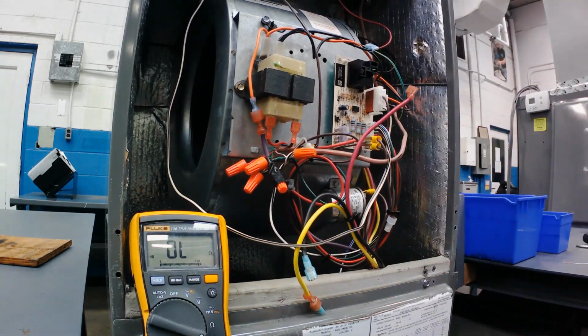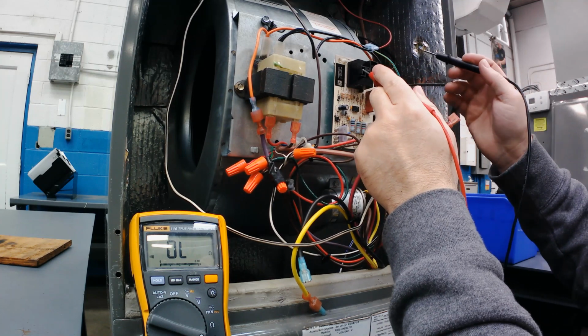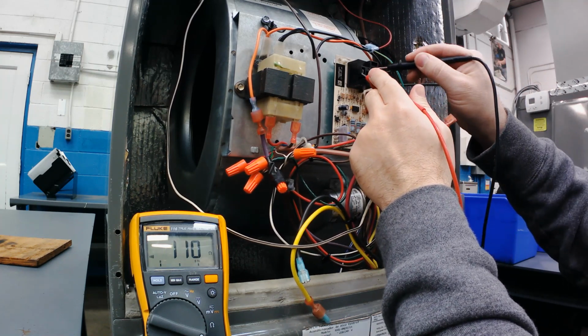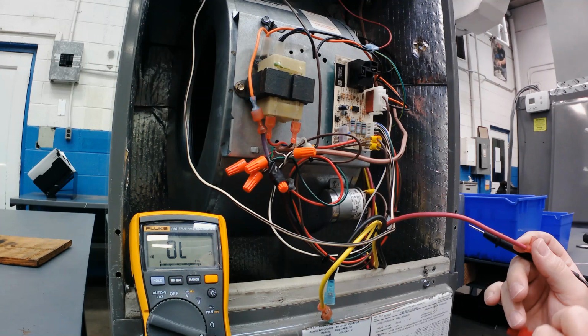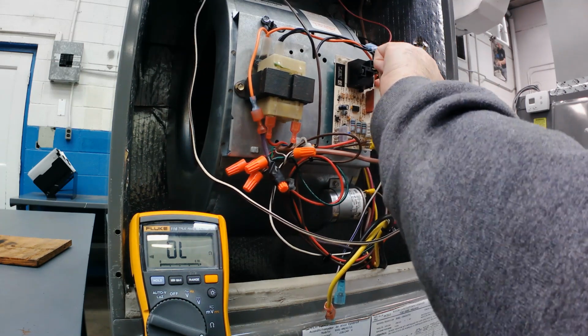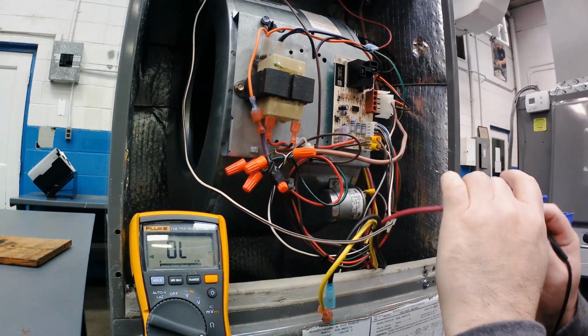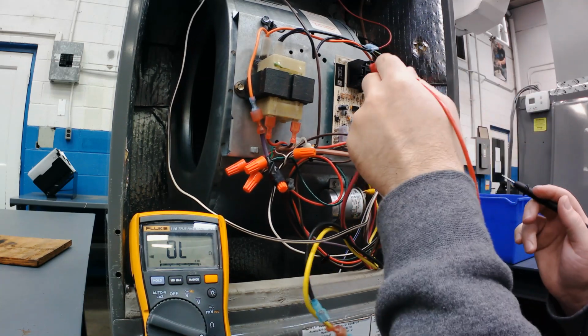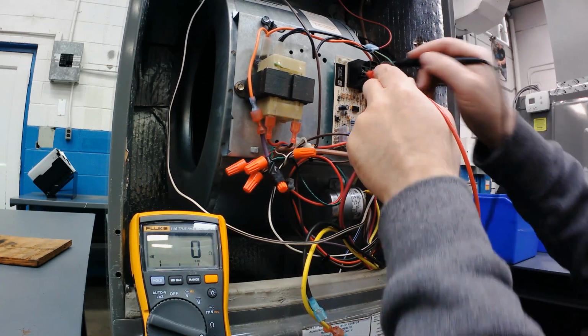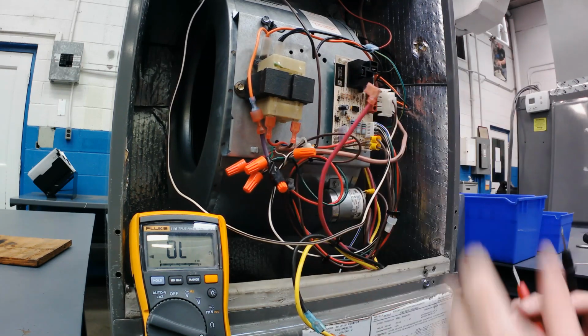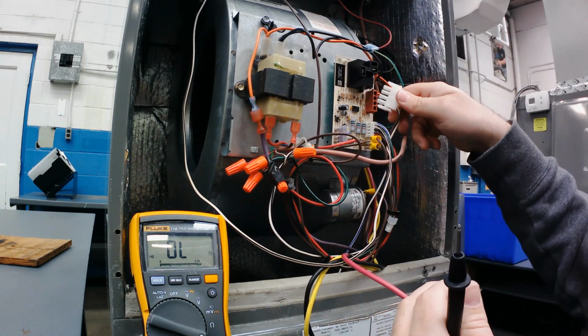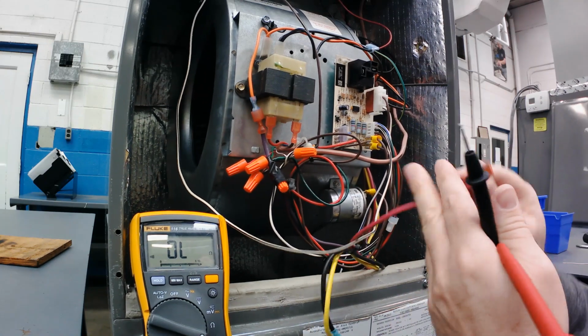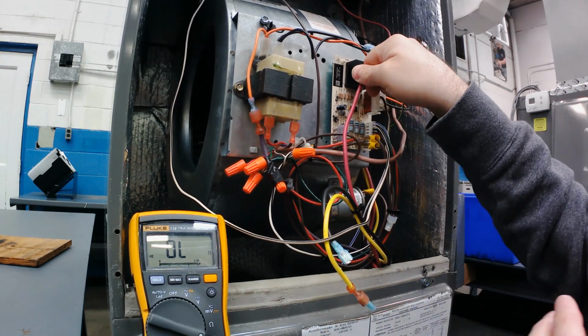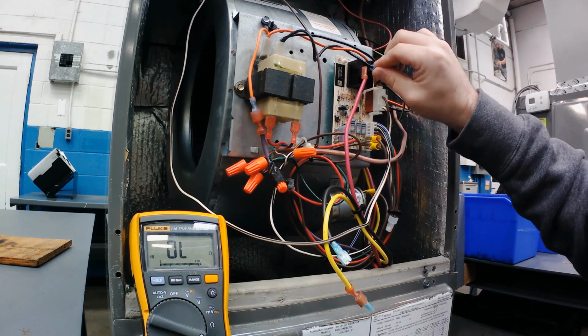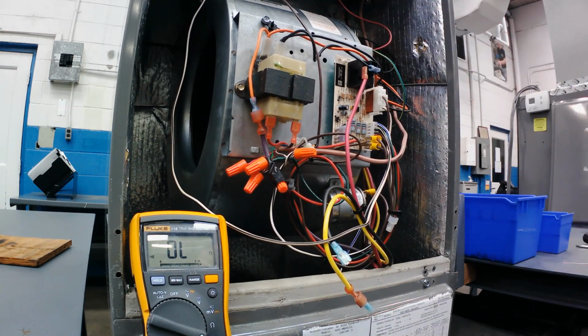And I take the high voltage off of the switch. So if I wanted to see if the switch is actually closed, I could do continuity through there, and by pulling the W off of it, that switch should open up in a few seconds or whatnot, and you could redo it again. Okay, so don't think that you have to keep all the wires on. You could easily pull them off to check continuity. You're not going to check voltage, necessarily, because you've pulled the voltage off. All right, so just another little tidbit.